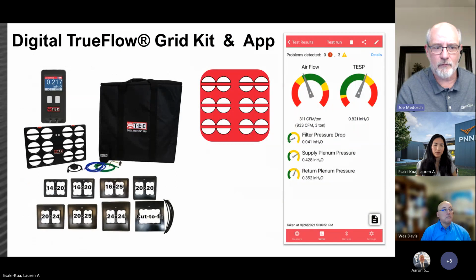Most of the stuff I had were really handheld, small devices, but people don't realize there's one major smart probe or smart device out there that will change our industry more than anything we have. It's great for measuring refrigerants and temperature splits and all that, but the one thing we're not doing very well is measuring airflow. It's something we've kind of failed at, and airflow also determines your charge.